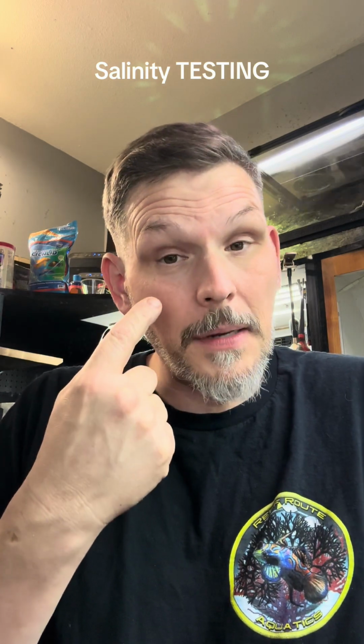Every single one of these comes with an operator's manual, and every single one of these says to either use RODI water or distilled. Do not do that, okay? I don't care what this thing says. Do not use distilled water or RODI water to calibrate your refractometer. And here's why. See that scale? If you're trying to set for 0, if you're off a little bit one way or the other, right? Again, the worst judge of anything is our eyes, right? So you could be off a hair one way or the other, just a fraction. But the problem is by the time that fraction actually gets up to 35 parts per thousand, or 1.026 in salinity, by the time you get up to that, it's off. Okay, so what do we use?